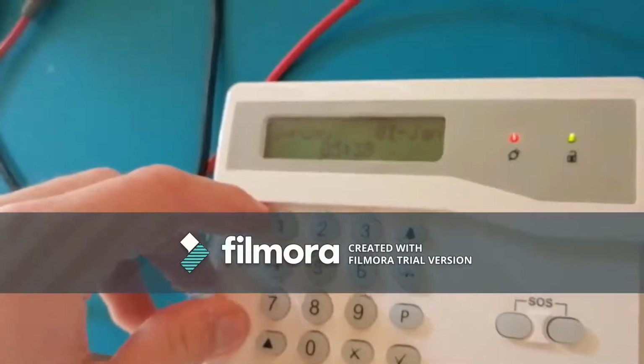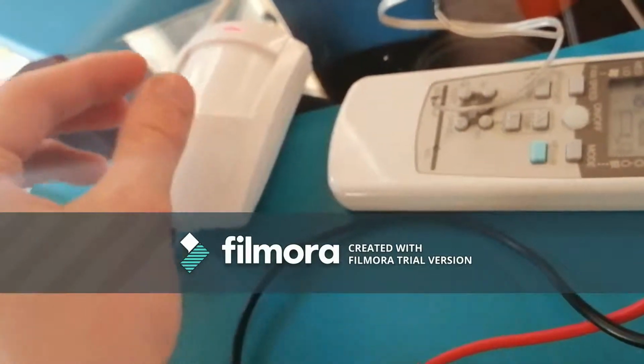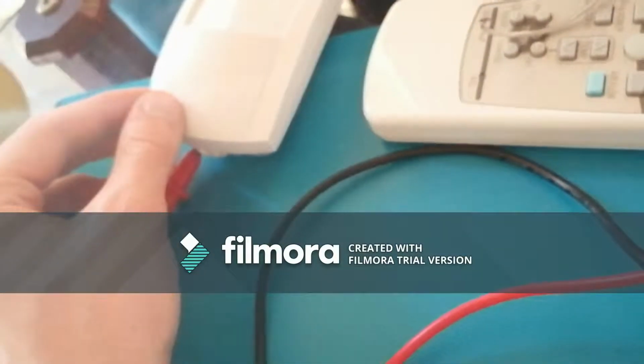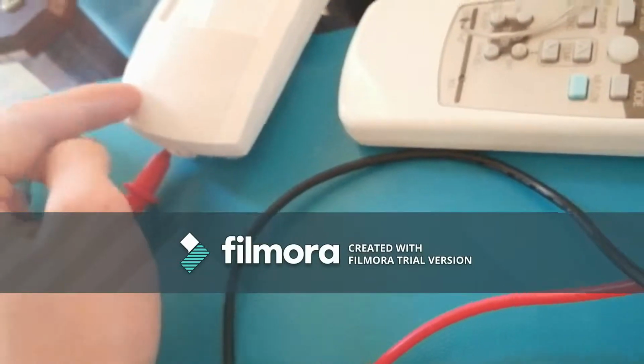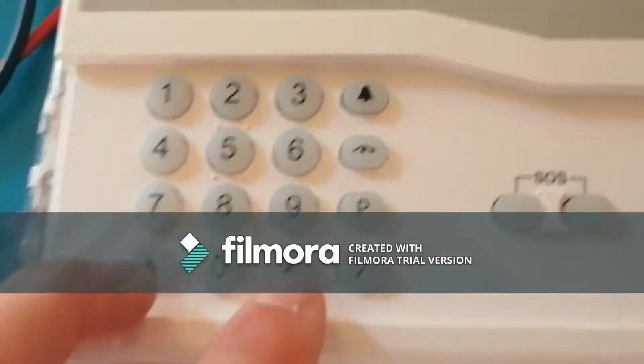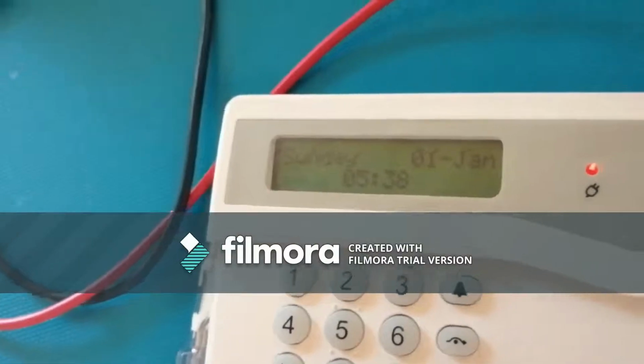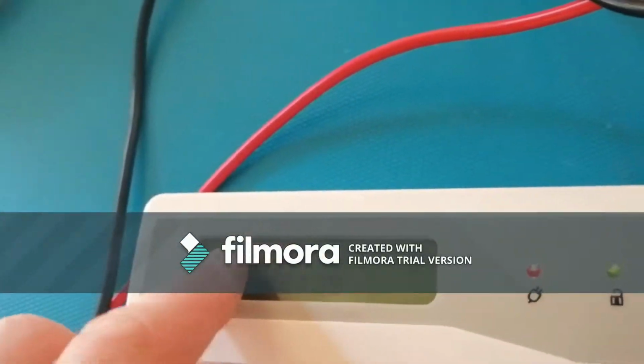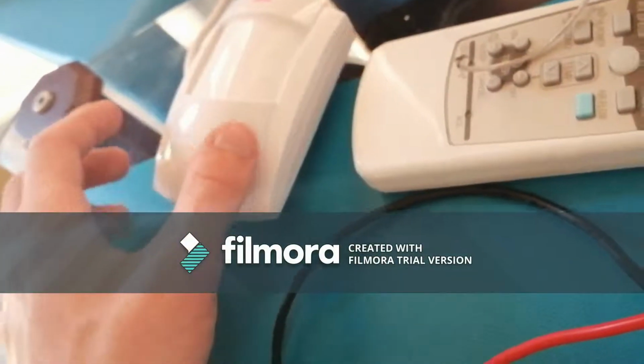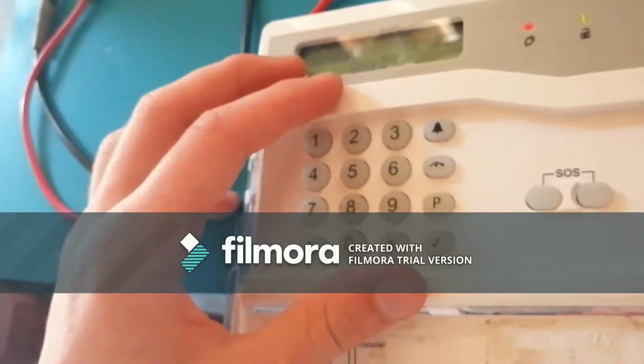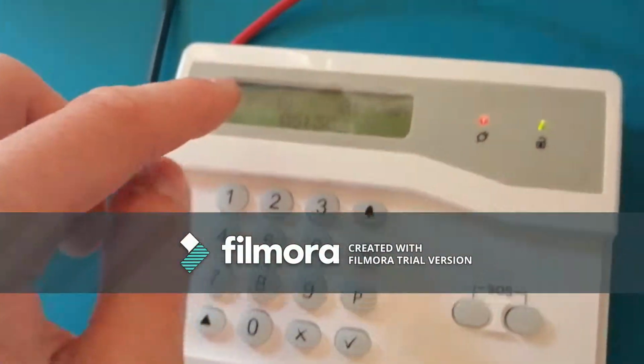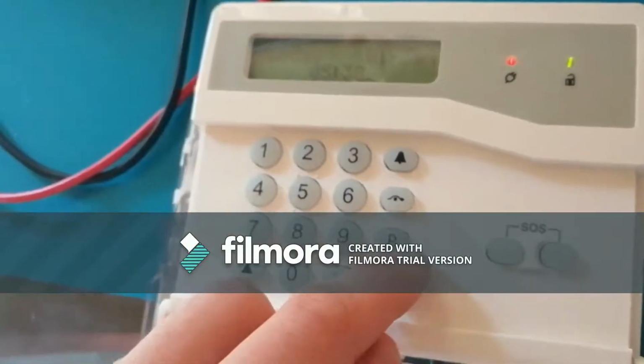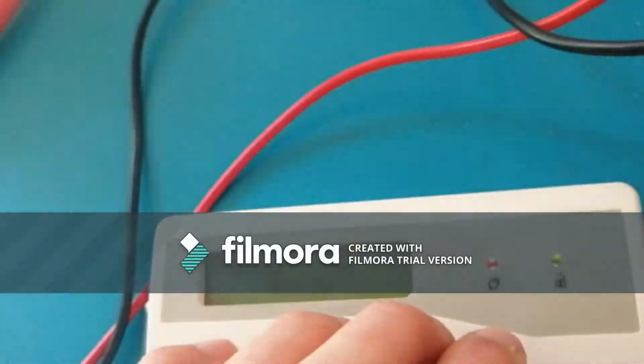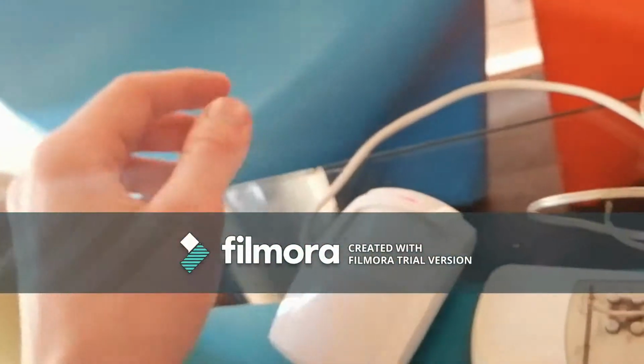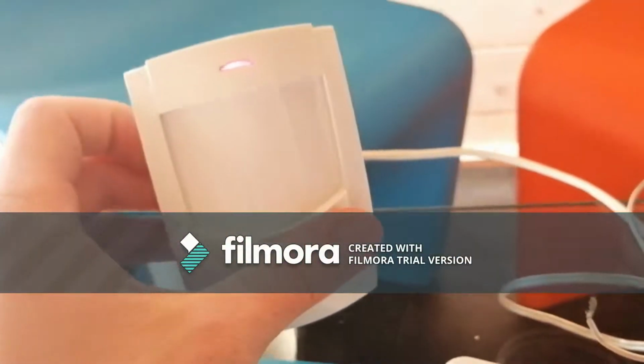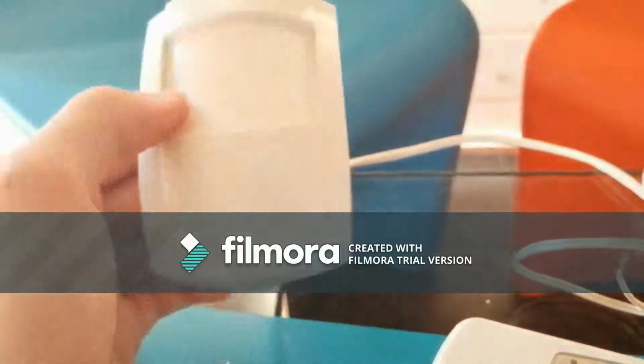Well, what you can try, with the detector all closed up and those 2 connections linked in the corner of the PIR, is to try and set the system again, and what you should notice is that the setting fault message for that detector should no longer be there. If it is no longer there when you try and set it, then you've identified that the cause of the fault is in fact the detector.